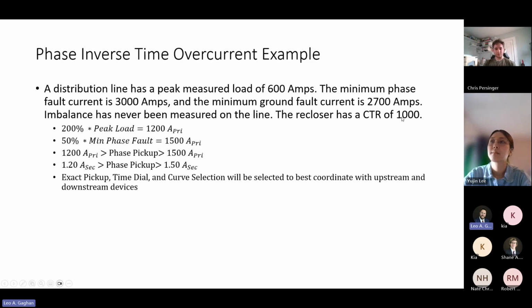Let's look at that CTR, because that determines what our device actually sees. So our setting needs to be greater than 1.2 amps secondary and less than 1.5. So that's how you're going to select your pickup. You're going to go through an exercise like that. Now, anything in this range is acceptable. 1.3 is acceptable. 1.4 is acceptable. It's up to you to decide where in that range to set it.